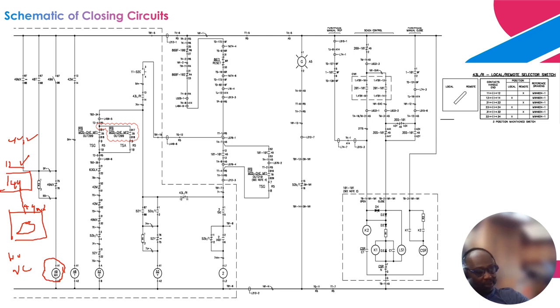And this is the coil for this 49 auxiliary relay, to be able to achieve the 24 volts contacts that you need, because the contacts are rated. If you use the contact for the wrong rating of voltage, the contacts are going to burn. So that is when auxiliary relays come into play. These are the two reasons. The first one is basically to multiply the contacts and use them for other functions. And secondly, if you need a contact to perform a function, and that contact requires a different voltage from the main relay, then that is when you integrate an auxiliary relay.